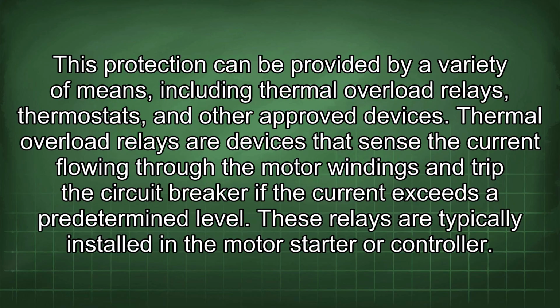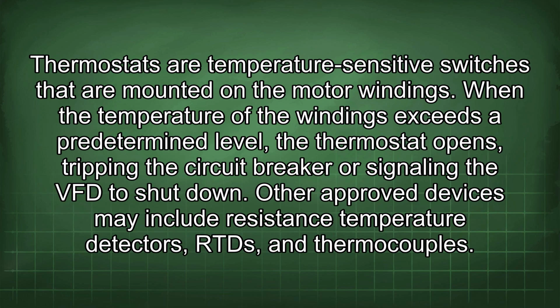Thermal overload relays are devices that sense the current flowing through the motor windings and trip the circuit breaker if the current exceeds a predetermined level. These relays are typically installed in the motor starter or controller. Thermostats are temperature-sensitive switches that are mounted on the motor windings. When the temperature of the windings exceeds a predetermined level, the thermostat opens, tripping the circuit breaker or signaling the VFD to shut down. Other approved devices may include resistance temperature detectors, RTDs, and thermocouples.